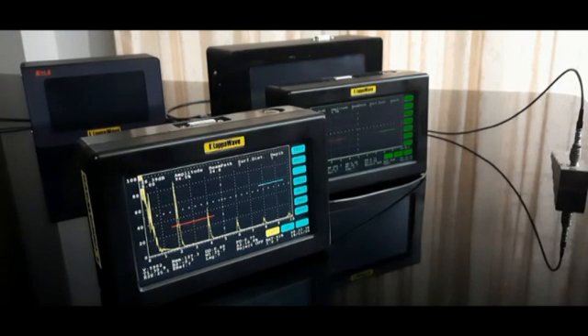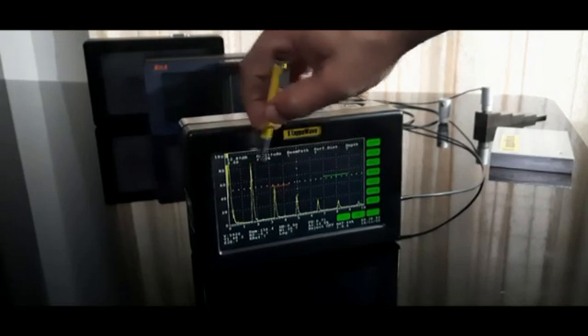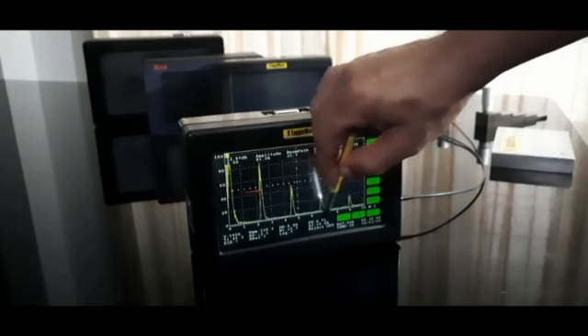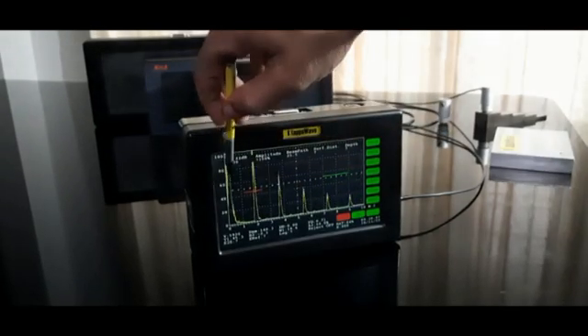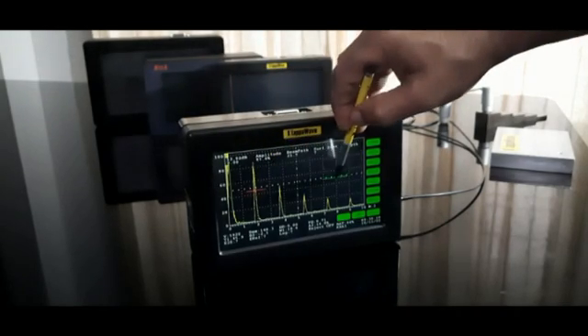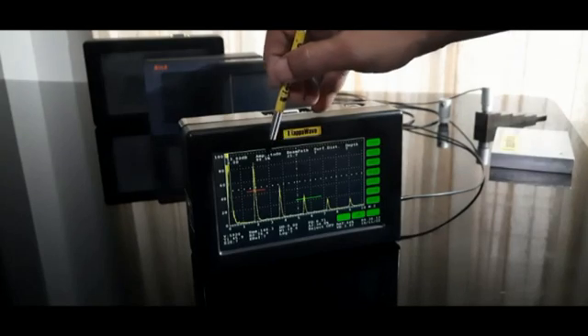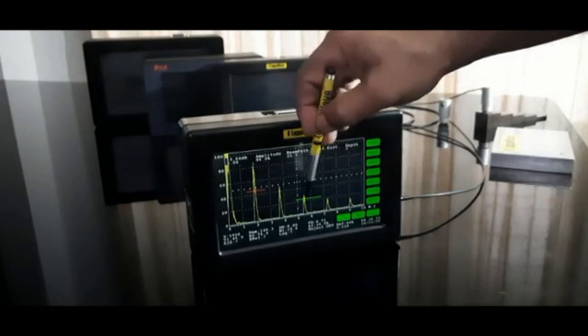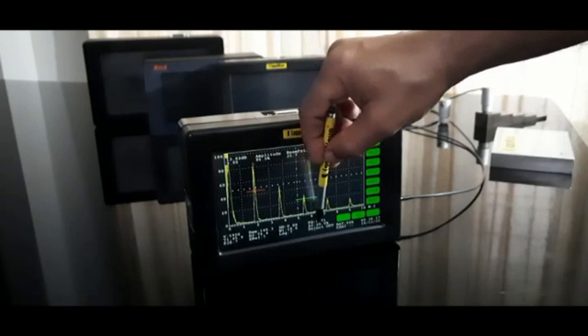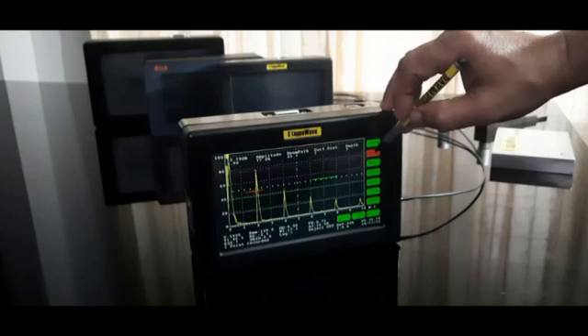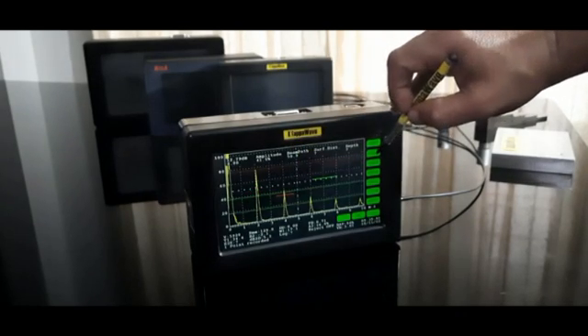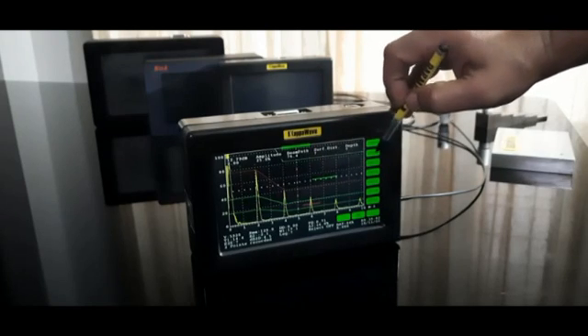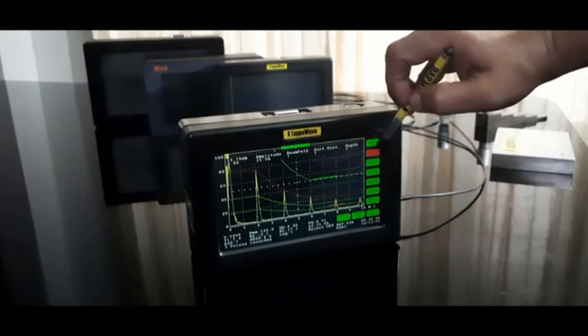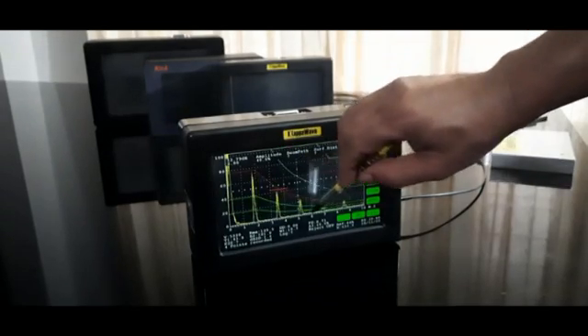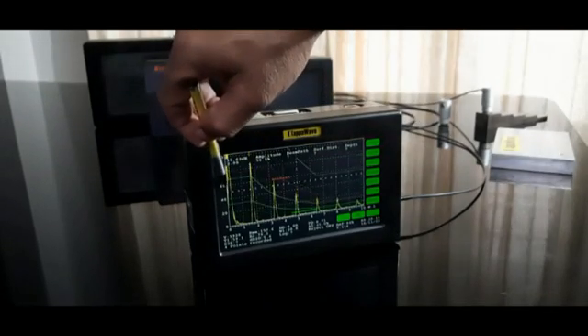Echo to echo readings can be easily taken by using a single gate. And construction of DAC becomes fairly easy. Place the gate on a signal and then click record. A 14-point DAC can be easily constructed. These are dynamic DACs that can be changed with range or amplitude.